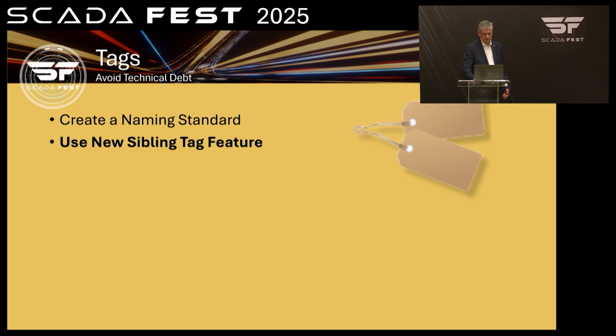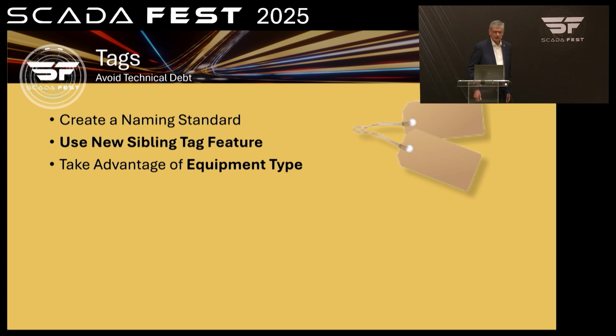There's a parameter in the I/O tags called equipment type. By default, pump is the only type delivered with the product, but you can add pH meters, flow meters, pressure transducers, temperature, anything at all. The idea is you put an equipment type on the I/O, which lets you find all these devices using the tag browser. Just go to the tag browser and filter by equipment type. If I want to find all my pH meters, I just select pH meters and there they are.